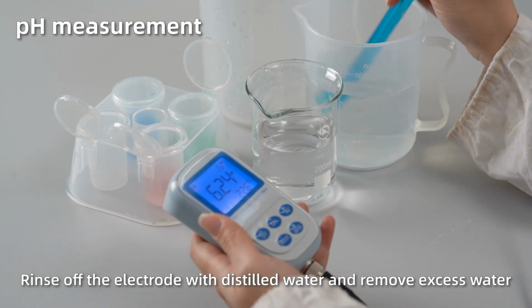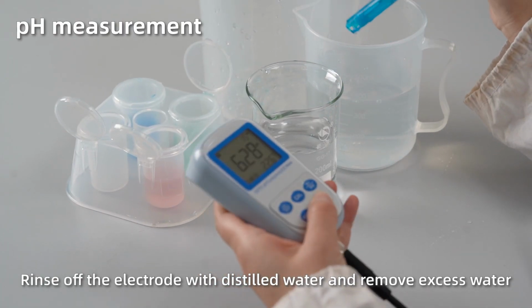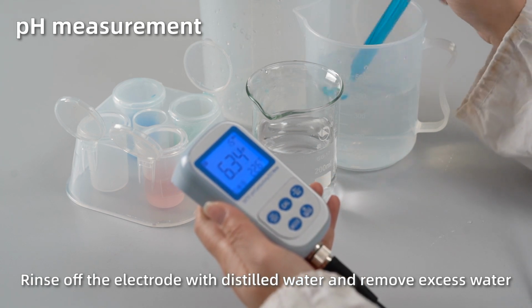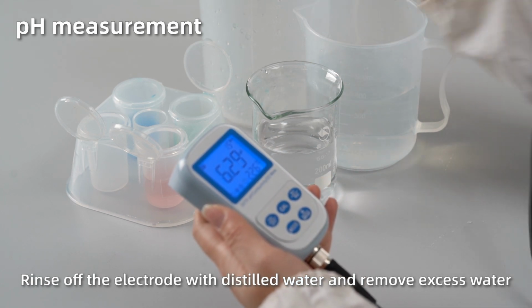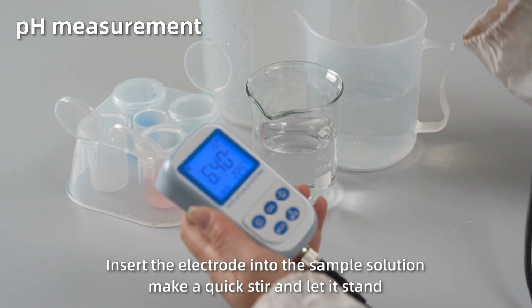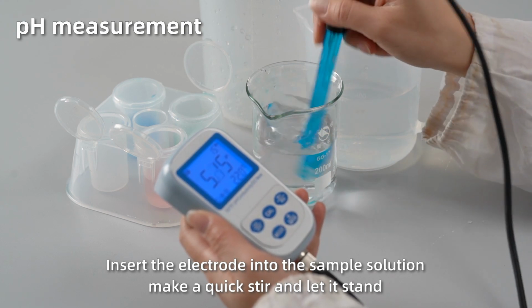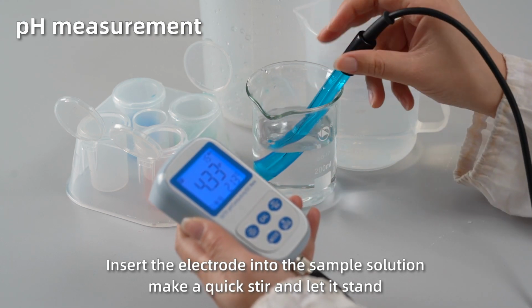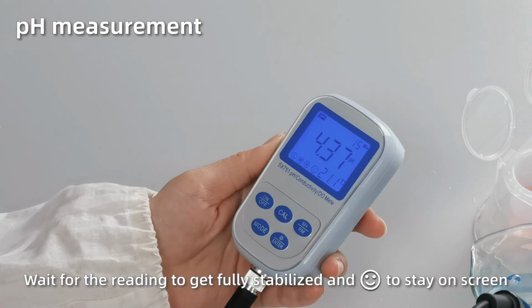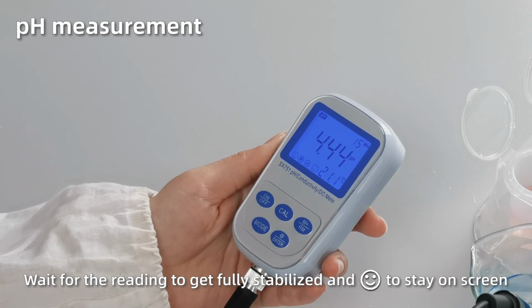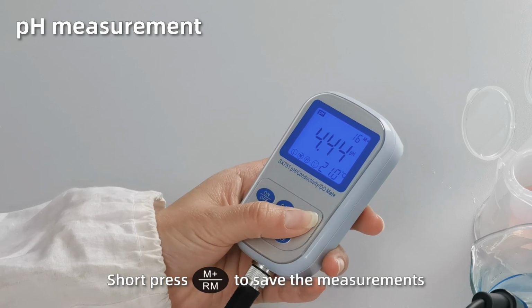pH measurement. Rinse off the electrode with distilled water and remove excess water. Insert the electrode into the sample solution. Make a quick stir and let it stand. When the reading gets fully stabilized and smiley face stays on screen, short press M+ to save the measurement.